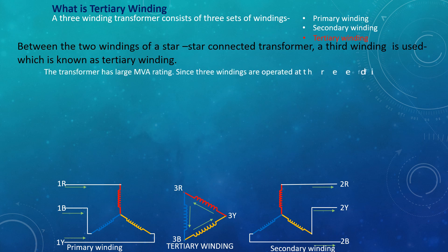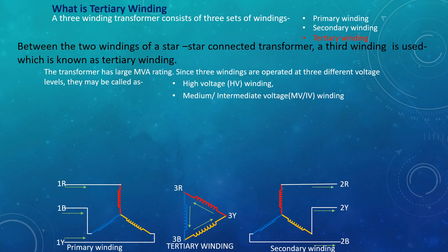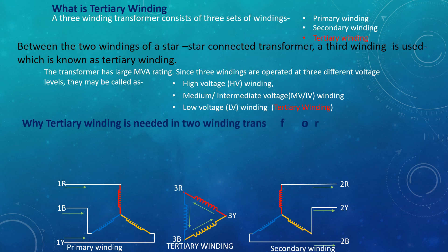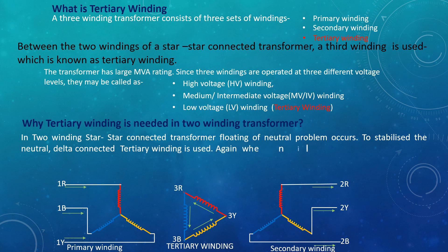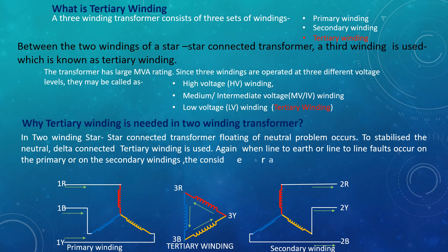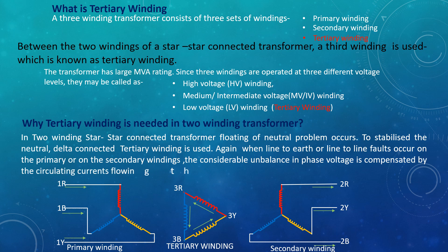The transformer has a large MVA rating. Since three windings are operated at three different voltage levels, they may be called high voltage winding, medium or intermediate voltage winding, and low voltage winding. Why is tertiary winding needed in a two-winding transformer? In a two-winding star-star connected transformer, the floating of neutral problem occurs. To stabilize the neutral, a delta-connected tertiary winding is used. When line-to-earth or line-to-line faults occur on the primary or secondary windings, the considerable unbalance in phase voltage is compensated by the circulating currents flowing through the closed delta.